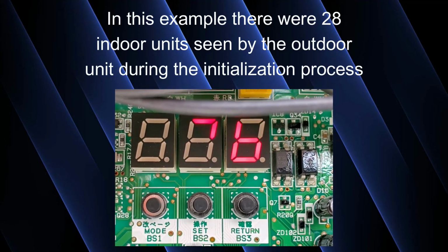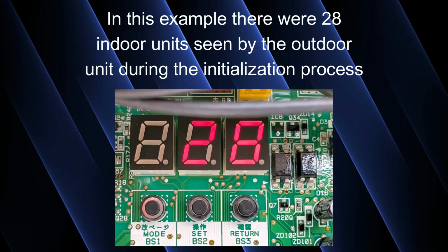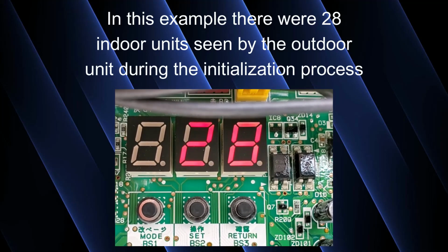Now, regardless if the number shown matches the number you installed or not, you need to escape out of that menu before proceeding to the next step. So to escape, anytime you're in any of these settings, simply press the mode button one time. Your newer boards will go back to a blank screen and your older boards will go back to H2P solid by themselves. Now, if the number of indoor units displayed does match the number you physically installed, awesome.